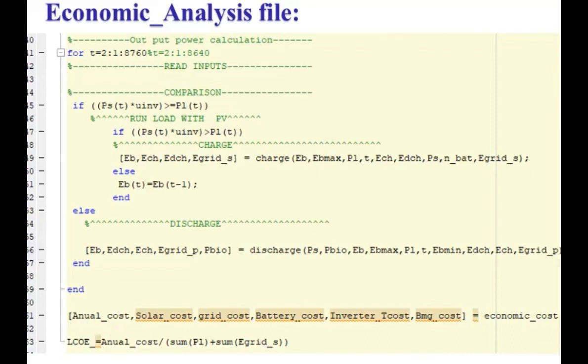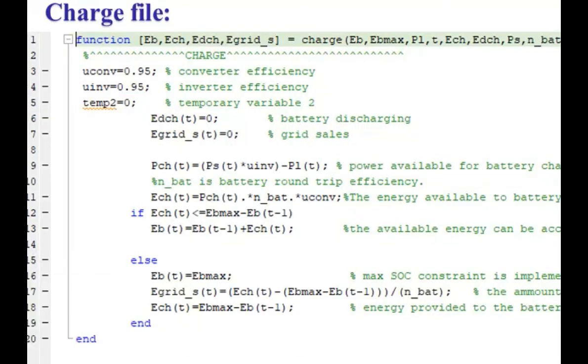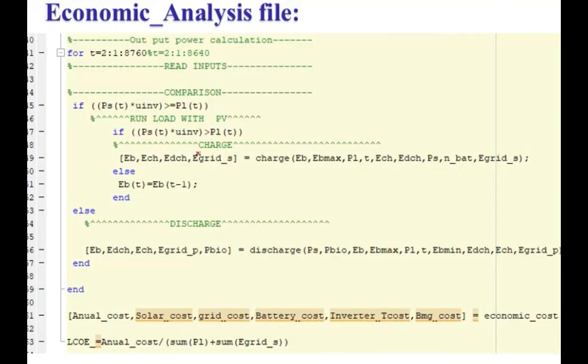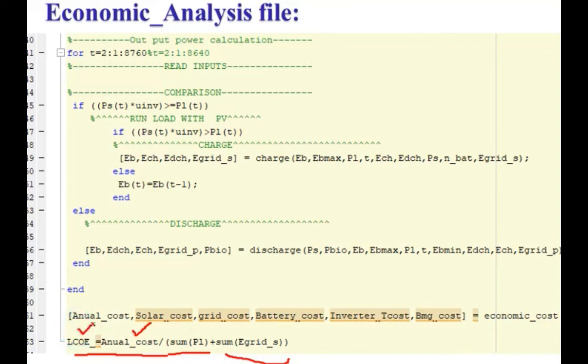The levelized cost of energy is calculated here. This is the annual cost divided by the energy provided to the load plus the energy that is provided to the grid, means the energy that is sold. If we divide the annualized cost of energy by the total energy provided by the system, it will give us the levelized cost of energy.